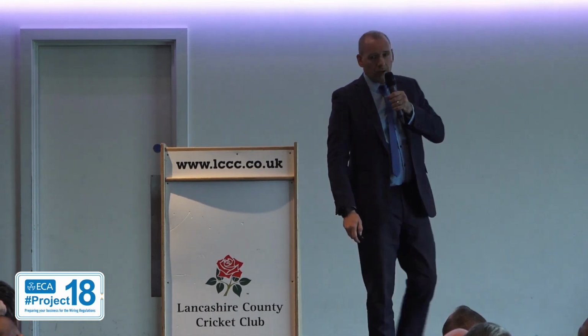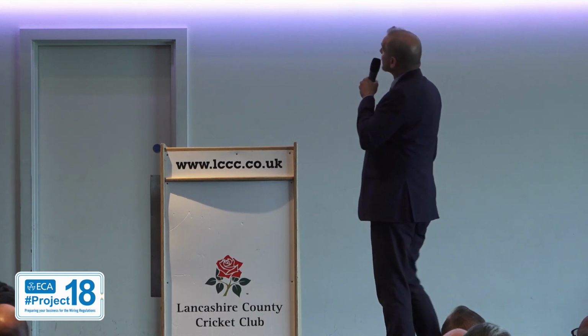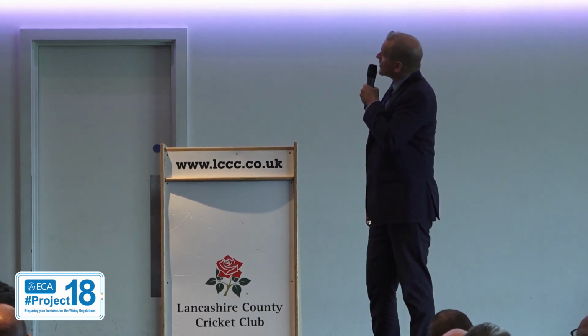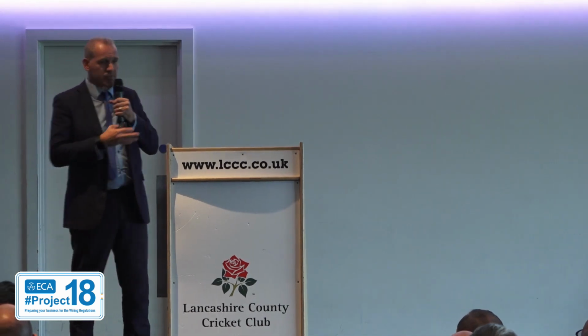So in terms of how do we do it, I could point you to BS 8519. The title for that, if you can't read that from there, is Selection and Installation of Fire-Resistant Power and Control Cable Systems for Life Safety and Firefighting Applications. It's a really good standard, and there's two key points in there that I'd pick out, sections 15 and 16, around cable installation practice and cable support systems. So effectively, the standard tells you how to set up your cable management system in escape routes and life safety areas. Some good pointers in there.